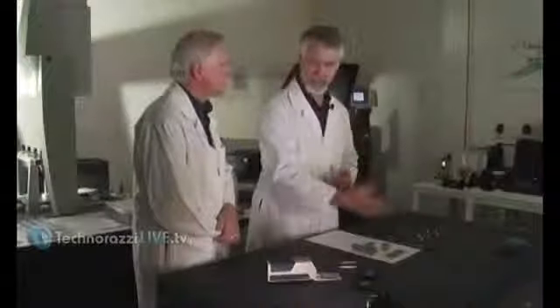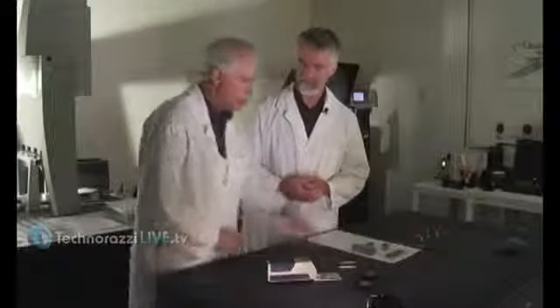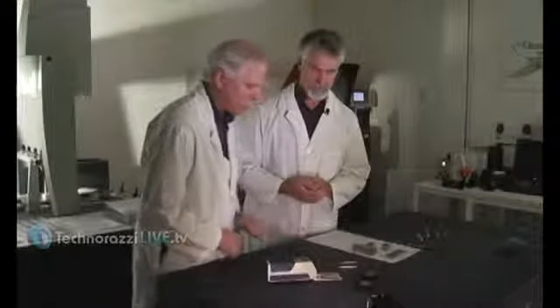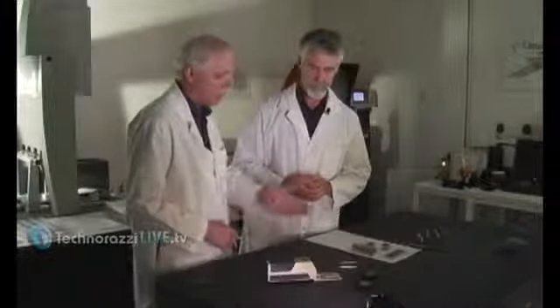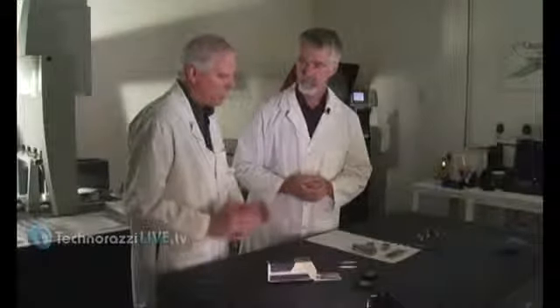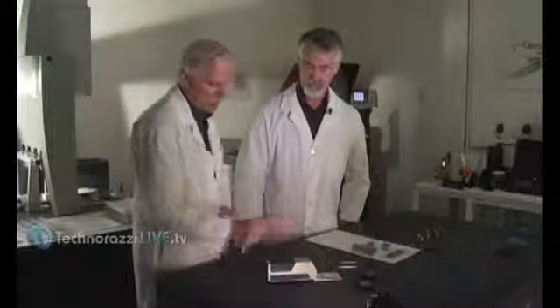Okay. So is there a rule of thumb as to what range you should be calibrating in based on the material that you know you're going to be measuring? No, you always use the provided standard, which is usually 116, 118, somewhere in that range. Sometimes 120. You'll find they're all manufactured there, and that's where the machines are set up. Then if you're measuring a finer surface, you'll reset the cutoff to match, but your calibration and your gain is set to the higher numbers.